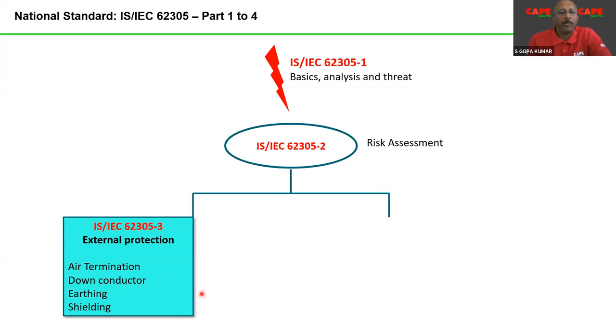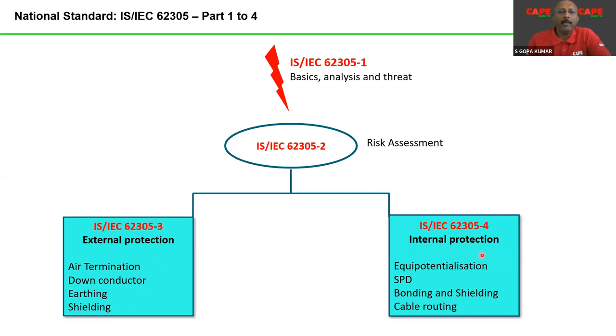Part three talks about external lightning protection. External lightning protection consists of air termination, down conductor, earthing, and shielding. Air termination at the top of the building: how you are avoiding a direct lightning strike into the building. Second, how safely you are carrying the lightning current from top to bottom of the building. The third one, earthing: how safely you are dissipating the current to earth. Shielding: how safely you are avoiding some kind of spark-overs and so on. Part four talks about protecting the internal parts of the building. Here the subjects are equipotential bonding, surge protective devices, bonding and shielding, cable routing and so on. So there are several components which have to be taken care of if you install a lightning protection.